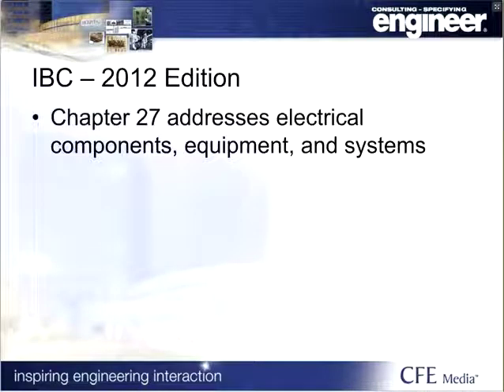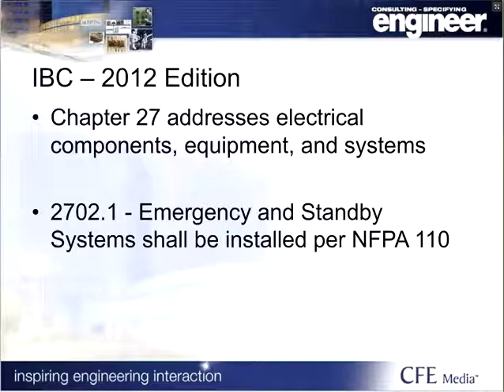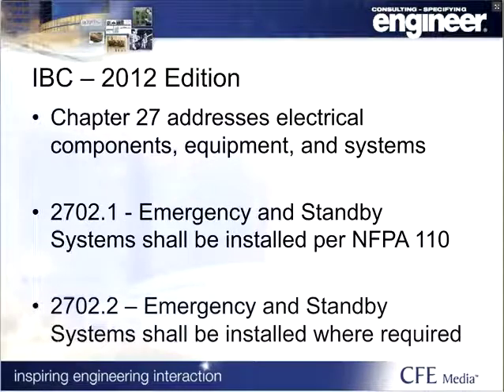IBC Chapter 27, Electrical, really doesn't go into too much detail in itself, but contains references to other chapters and sections where emergency and standby power systems must be provided. Section 2702.1 specifically references NFPA 110, and that emergency and standby systems required by that code must conform to it. Section 2702.2 goes into the references to other sections such as egress and exiting, group occupancies, and high-rises.